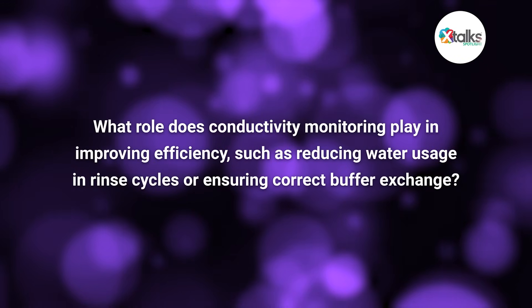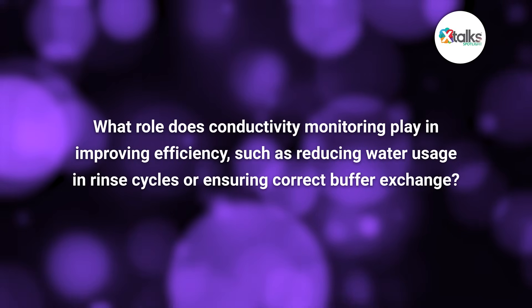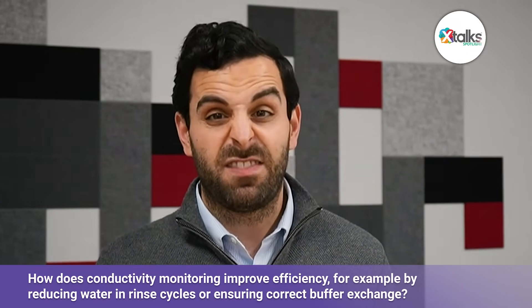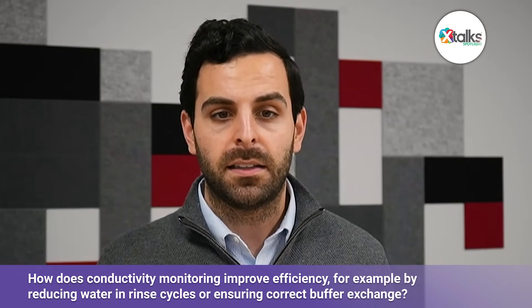And Eric, what role does conductivity monitoring play in improving efficiency, such as reducing water usage in rinse cycles, or ensuring correct buffer exchange? This is a great question because it's where conductivity shows its value beyond just compliance. When you're doing rinse cycles, without sensors, you'd probably rinse for a fixed amount of time — let's say 20 minutes — just to be safe. But in reality, the system might be clean in 5 or 10 minutes. Conductivity monitoring data lets you see when the water is truly back to baseline, so you can stop rinsing right at that moment.